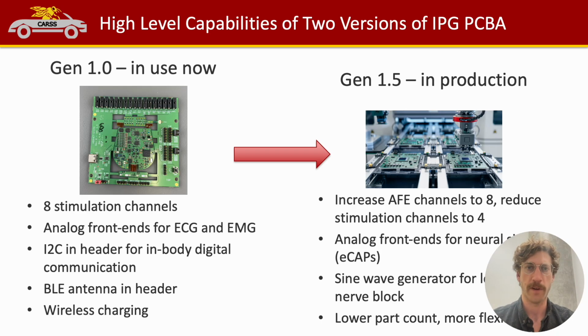For Gen 1.5, this board is now in production. And for this, we've actually increased the AFE channels. So now there are AFE channels for neural signals for ECAPs. However, we have decreased the stimulation channels down to 4. One thing we've added for all of the stimulation channels is a sine wave generator. This will allow us to output a low frequency sine wave that we can use for directional nerve blocking. So we can output a sine wave to block signals in one direction and then stimulate in the opposite direction.